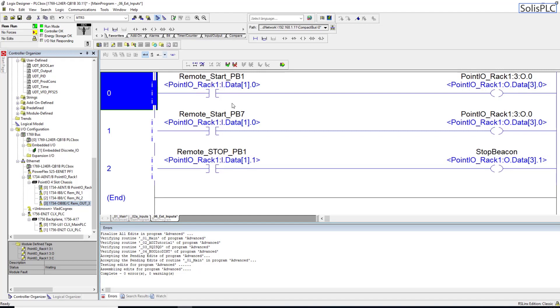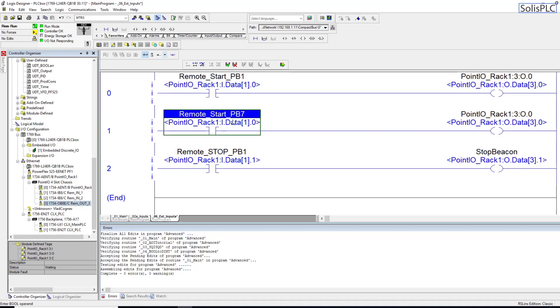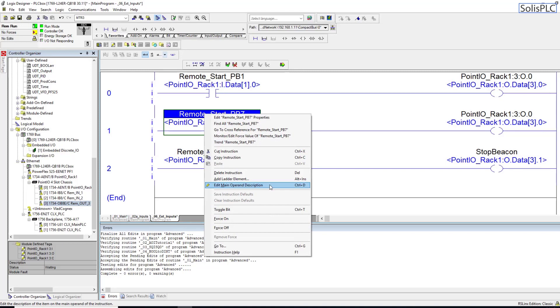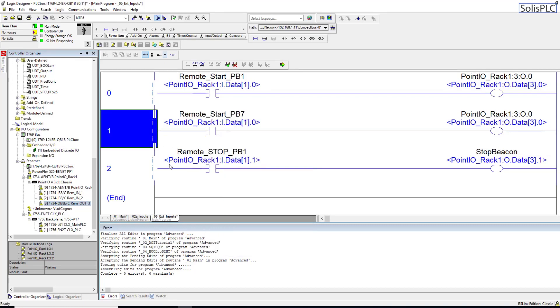If you're working with RSLogix 5000 or Studio 5000 version 21 and over, there's not a whole lot of benefit in using alias tags because you can use the description. When you right click this and add a description, this works just as well because the description is stored on the PLC. But when you're working with RSLogix version 20 and below, the comments or descriptions are not saved on the PLC, so you risk losing those descriptions whenever you don't save the program but rather upload from the PLC.